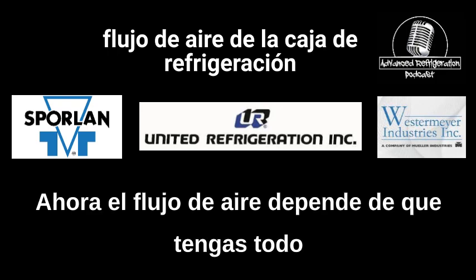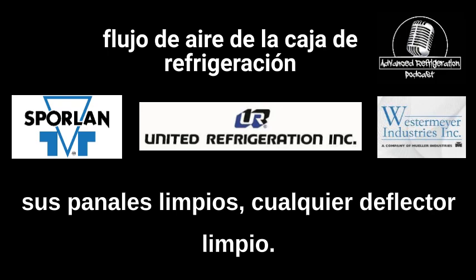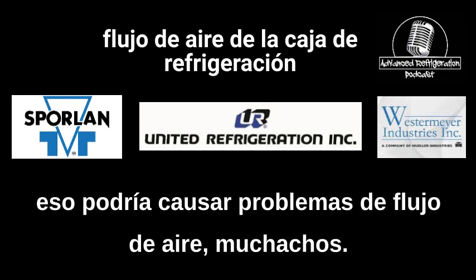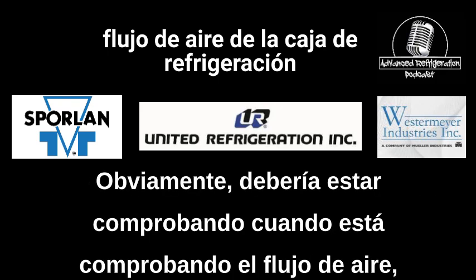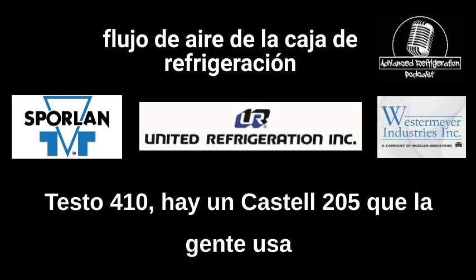Now, airflow is dependent on you having all your motors going, all your coils cleaned, all your honeycombs cleaned, any baffles cleaned. There's a lot of different things that could cause airflow issues, guys. It could be, go ahead, Brett. Oh, the baffles is one thing I want to hit on. Obviously when you're checking airflow, you want to check it either with an Alnor Junior or a Testo 410A.